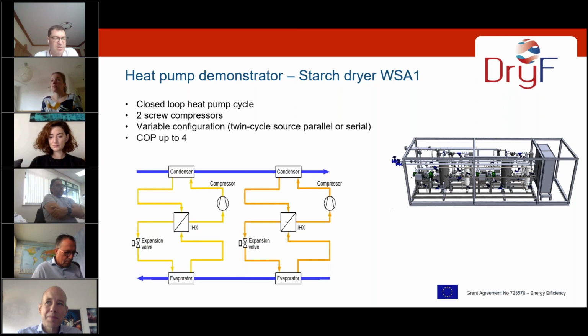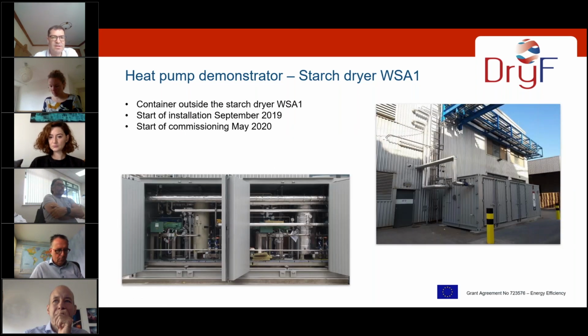So to bring all the necessary parts to our factory, a container outside the starch dryers is used for all the housing of the equipment, including all measurement and control systems. The 3D scheme you can see here on this right-hand side picture. And on this screen you can see two pictures during installation at the end of September 2019, starting at the beginning of 2020. We had a little delay due to Corona, so we started the commissioning of the whole heat pump at the end of May 2020.